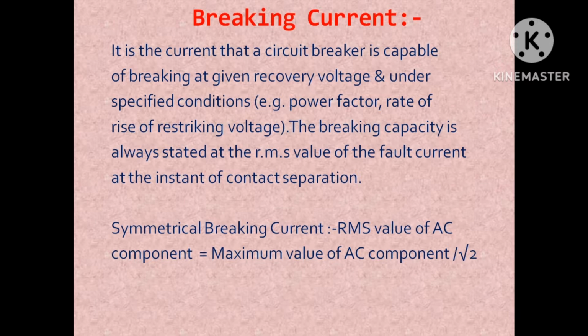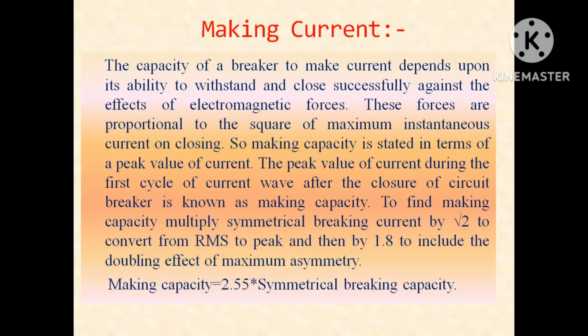Breaking current refers to the RMS value of the fault current at the instant of contact separation. In this model of breaker we are discussing, 40 kiloamps is given as the breaking current. One more point is the making current. It refers to the maximum peak value of the fault current, and breaking current refers to the opening of breaker contacts during the time of faults. Making current refers to the closing of breaker contacts during the time of faults. So whenever a fault persists and the breaker is closing under fault conditions, the breaker contacts should tolerate that mechanical and thermal stress. So the making current is always given as 2.5 times the breaking current.